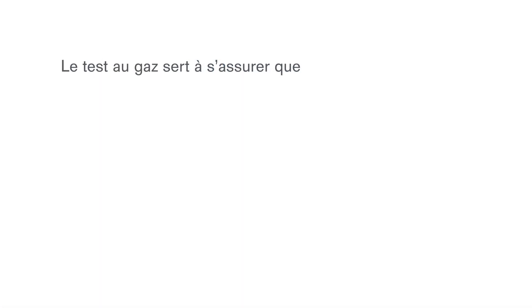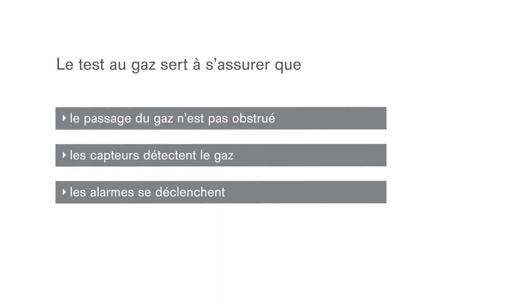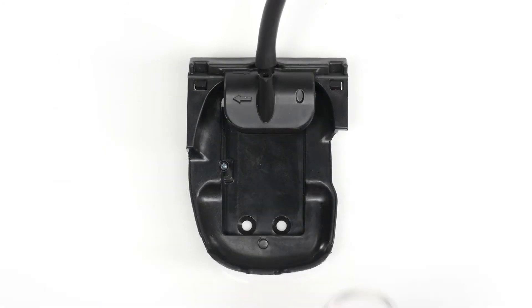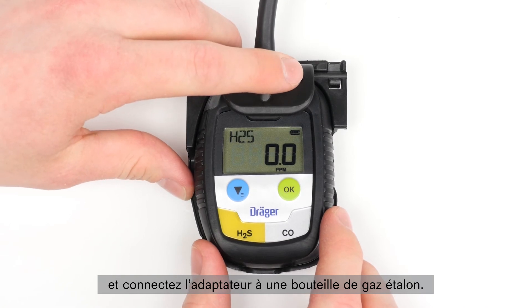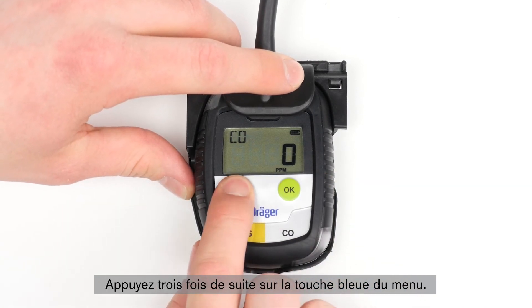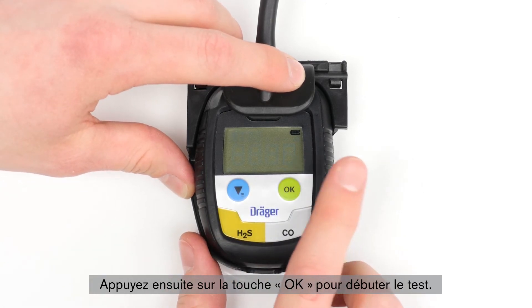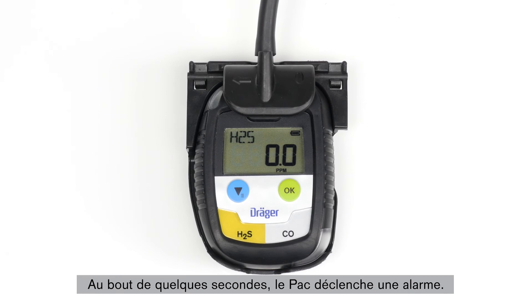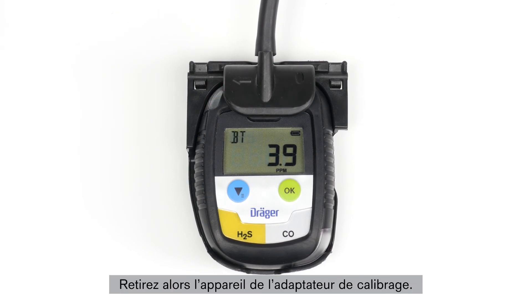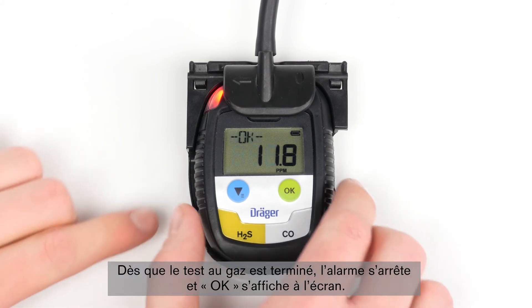A bump test determines whether the gas path is blocked, the sensors detect gas, and the alarms are set off. In order to conduct a manual bump test, attach the device to a calibration adapter and connect the adapter to a test gas cylinder. Press the blue menu button three times in a row, then press the OK button in order to start the test. BT simple will appear on the display for the current bump test. After a few seconds, the Draeger Pac will activate the alarm. Remove the device from the calibration adapter. As soon as the bump test is completed, the alarm stops and OK will appear on the display of the device.